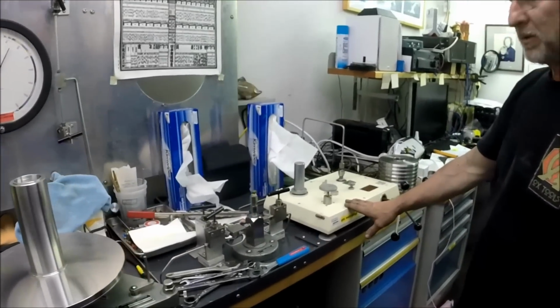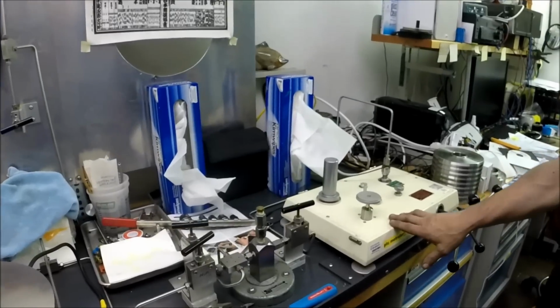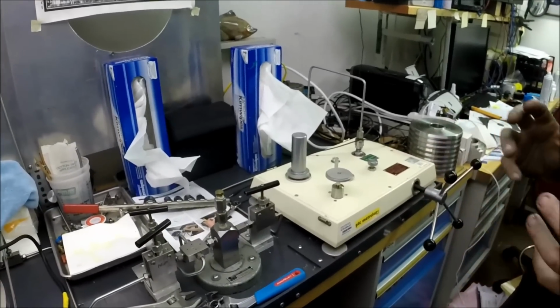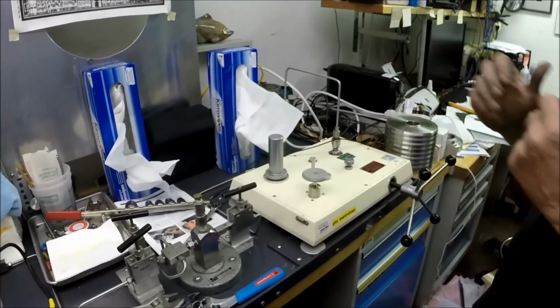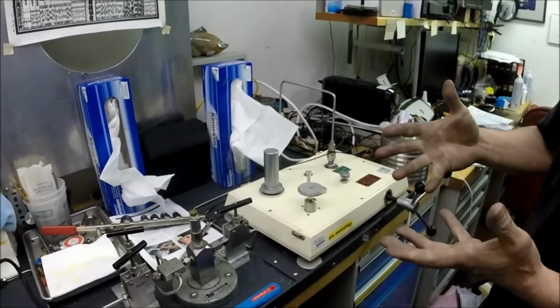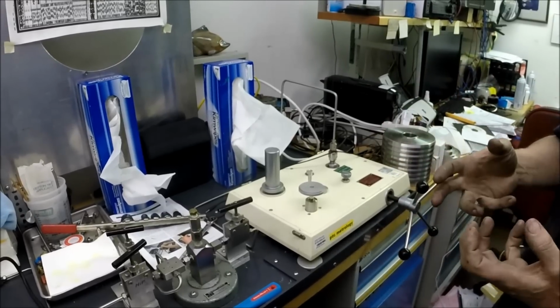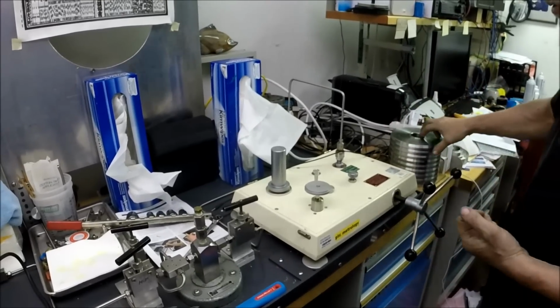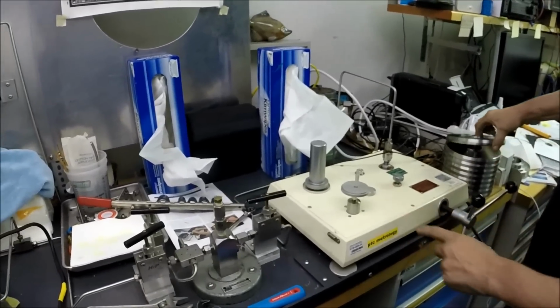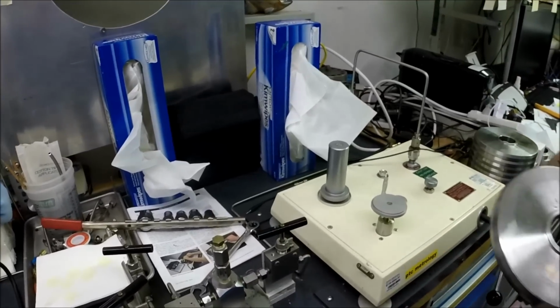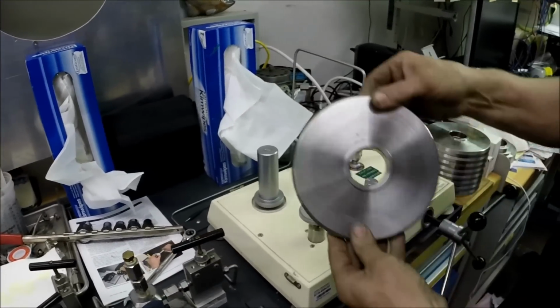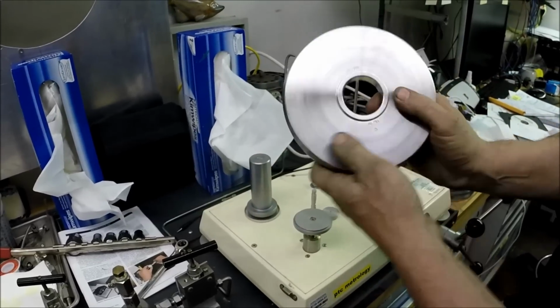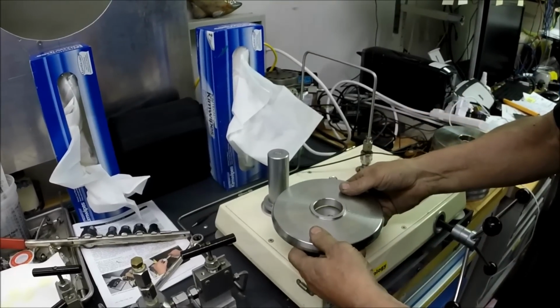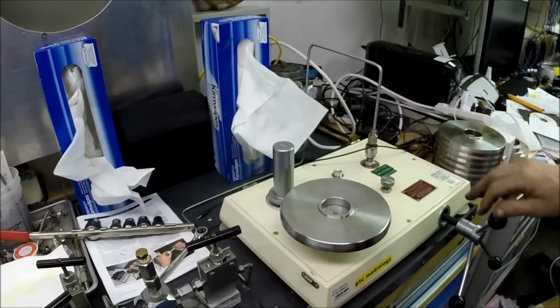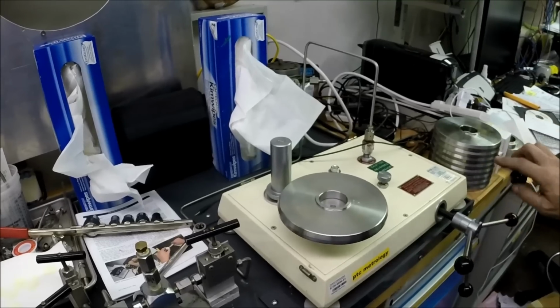It's called a dead weight tester, and what it does is it applies a certain amount of weight over a certain area. So if you wanted 100 psi, you would essentially put 100 pounds on 1 square inch. That would generate 100 psi. This platform generates 2 psi all by itself. This is a 50-pound platter, so 50 plus 2 would give you a total of 52 pounds.